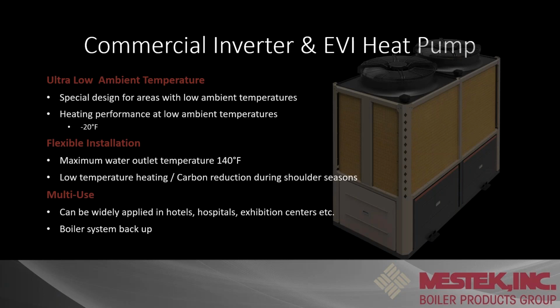So, ultra low ambient temperature, like I already said, it's designed for lower ambient areas, but also works in Florida, California, areas of that nature as well. You actually get probably more heat capacity out of it the warmer it is, and again, I'll show you that. That water temp at 140, and then we'll touch on multiple use.